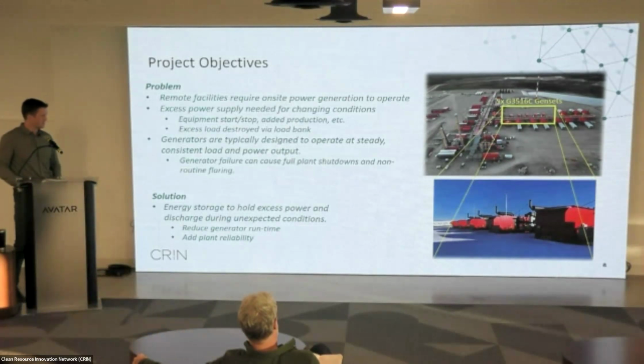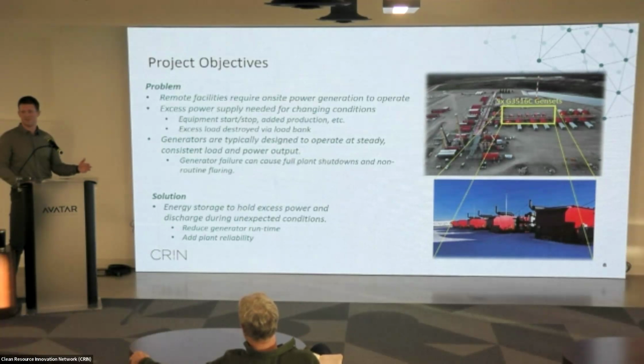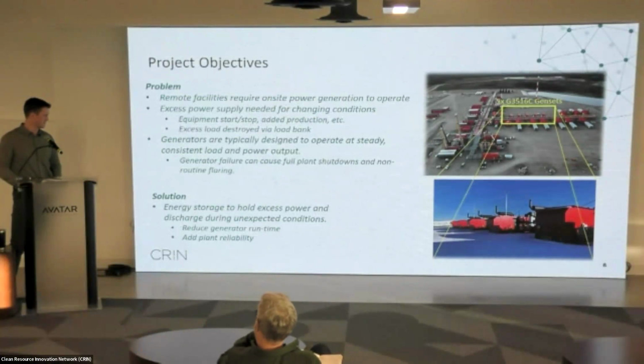These generators are typically designed to operate at a steady, consistent load, which means you often run them in excess. If they go away from that steady load, they can go down on failures and create a domino effect through all your generators, causing a full plant shutdown, which ultimately leads to additional non-routine flaring as a safety precaution with various shutdowns.